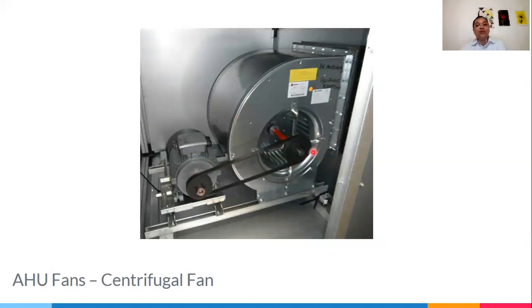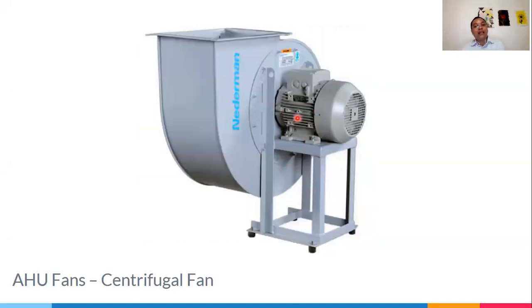With the belt and pulley system, you have to realign and adjust it every now and then. Every maintenance period, you have to check, laser align, check the tightness of the pulley, and replace the belt. But since these are coupled directly, that requirement is gone, assuming this motor is equipped with a variable frequency drive. So the speed of rotation is no longer controlled mechanically — it's controlled electrically.